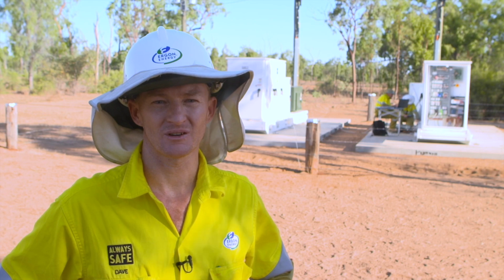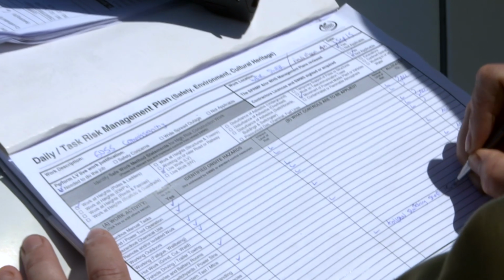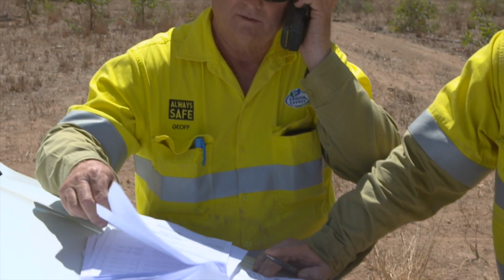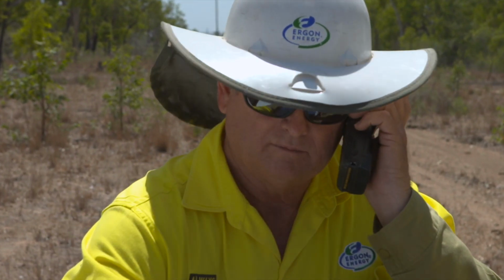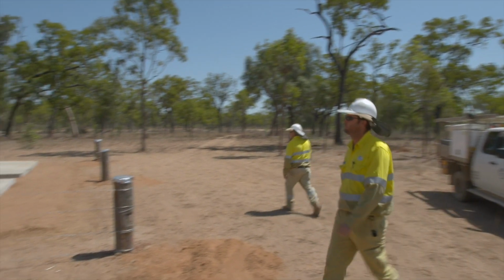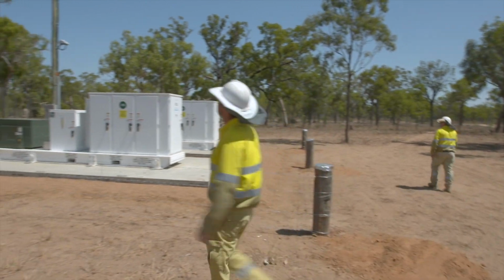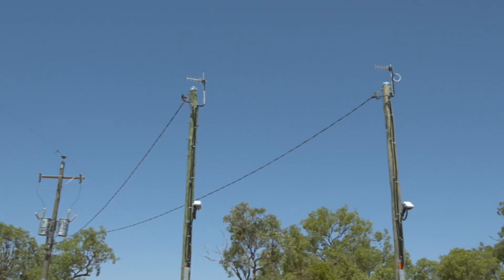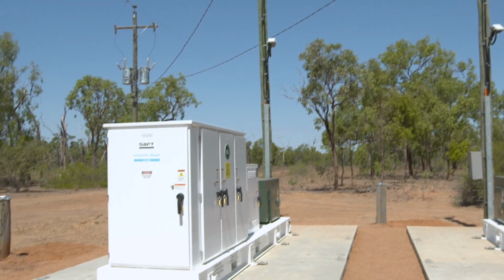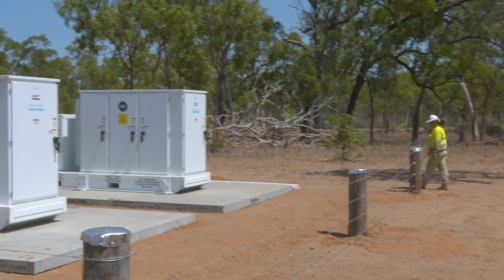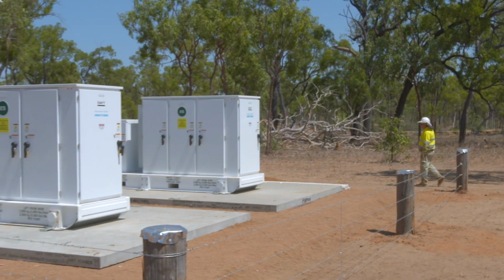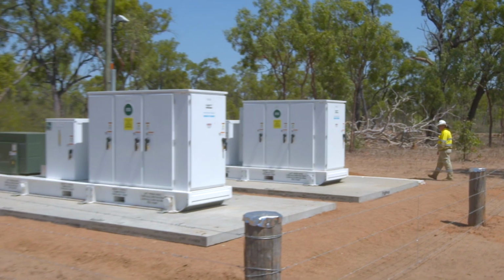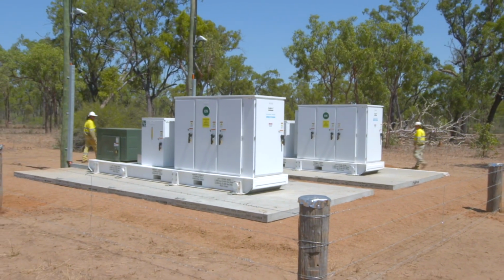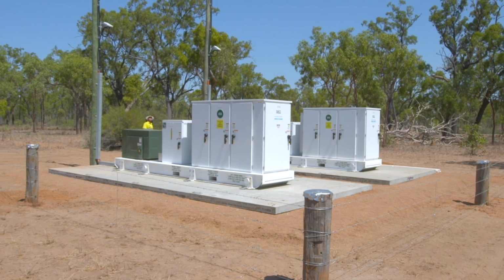When you arrive on site and after you've completed your on-site risk assessment, notify the GUSS engineer prior to starting work. From a safe distance of approximately 10 metres, perform a ground-based visual inspection. Look for physical damage, oil leaks, smoke, wires down and perform a pole top inspection of the distribution substation. Report any unit defects to the GUSS engineer and distribution substation or HV network problems to the OCC.